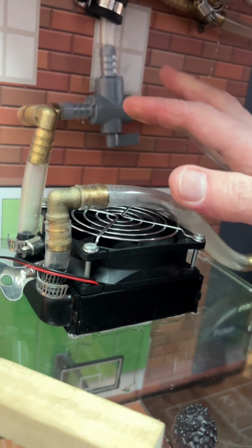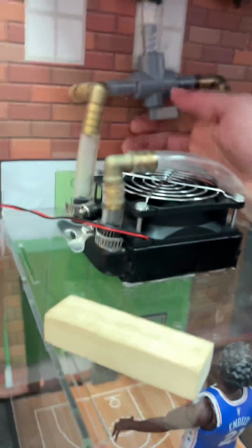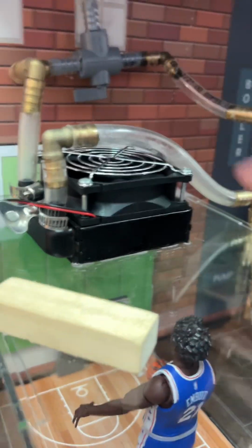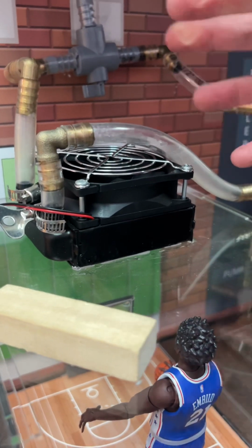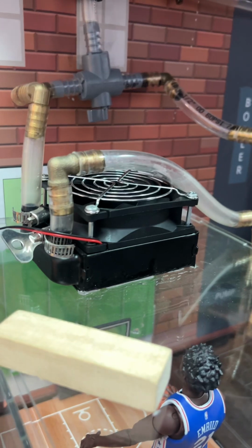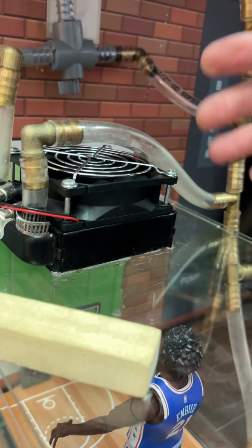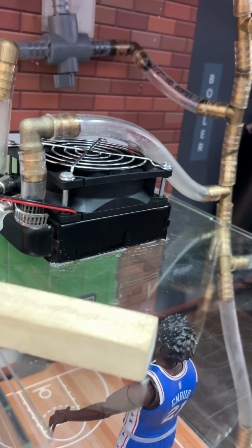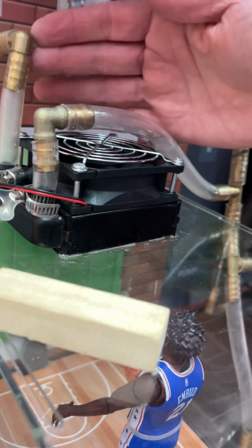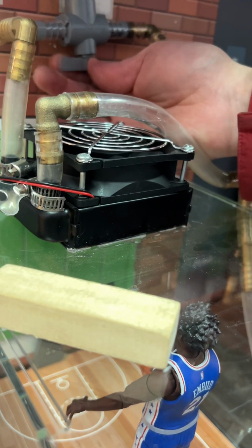This is very similar in operation to what the actual building has, except that in the actual building, these valves are controlled by electronic digital controllers that modulate them, so they don't just send heat or no heat to the room, or cool or no cool. They modulate, so it'll send a portion of the flow through this coil. As the room gets closer to set point, it'll start to throttle back. If the room needs more heat, for example, it'll send more flow through the coil. But in the actual building, this is a modulating, digitally controlled device.